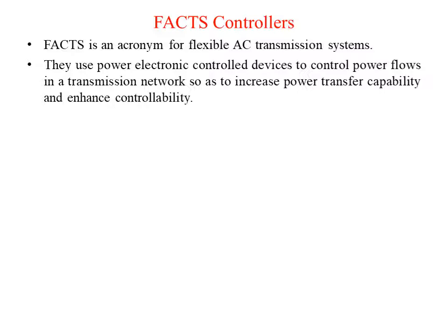If we compare all these four methods, HVDC, FACTS controller, and the tap changing transformer were the superior methods in which we can use the transmission line to its highest capacity, whereas there is a drawback in the case of impedance: the impedance overloads the line and there can be voltage collapse in the case of impedance control.